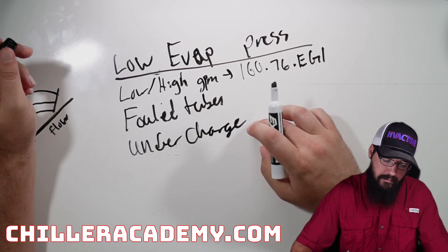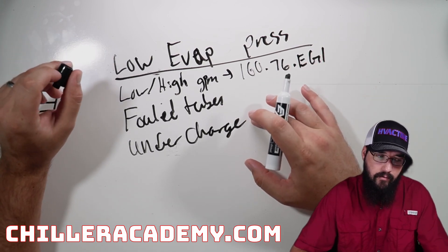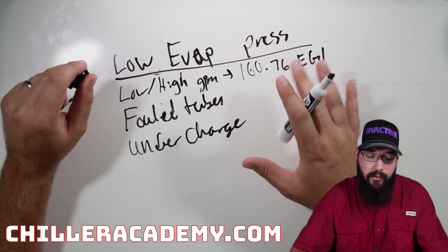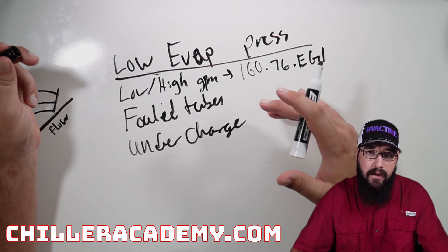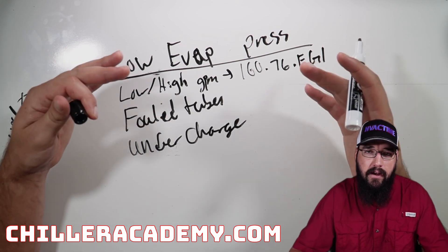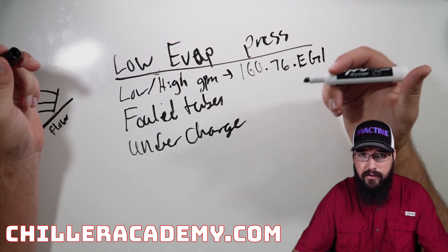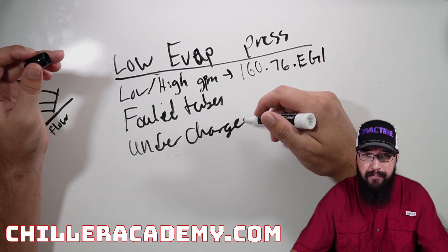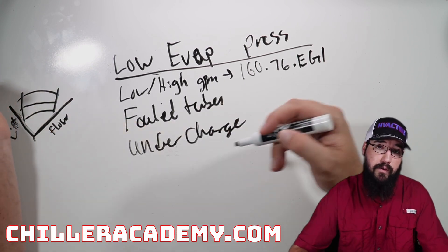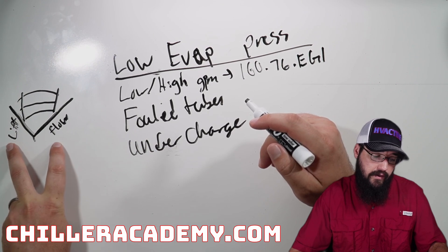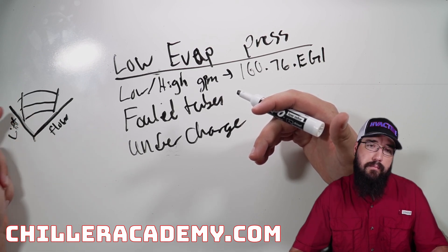Undercharge — going back to the metering device failure scenario — is going to starve our evaporator. Even if the metering device is working but we're maintaining condenser level correctly yet cannot get our level up in the evaporator, that's what undercharge starts to look like. You won't be able to maintain evaporator level, but you'll still have condenser level since that's what we control off of. If neither can satisfy, you've definitely got a big issue — that's a clear undercharge. Undercharge pushes your pressure down, creates a higher lift condition, and dramatically reduces volume, which plays heavily into where we are on the surge graph.